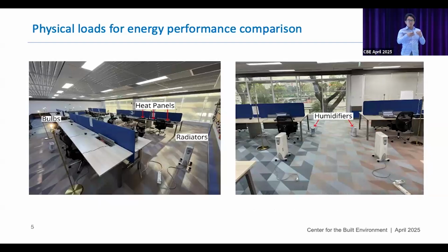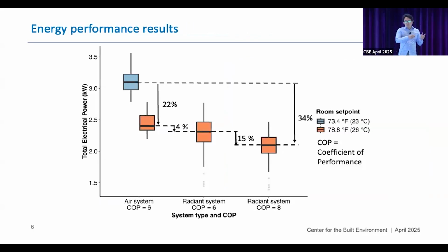For the energy evaluation, we place multiple physical loads of bulbs, heat panels, radiators, and humidifiers to simulate occupancy load. I won't go into detail, but essentially we are simulating partial occupancy, medium occupancy, and maximum occupancy of the space. You can see from the results for the air system, we did a 23 degrees Celsius, 73.4 degrees Fahrenheit set point, because that's the baseline in Singapore. In Singapore, people usually set it at around that set point for office cooling. And we also did 26 degrees Celsius, which is 78.8 degrees Fahrenheit, for the air system.